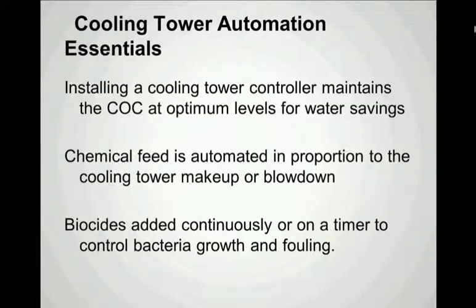So in essence, cooling tower automation is a big help in terms of keeping the cycles of concentration at optimum levels for water savings. It also helps us manage the chemical feed to make sure that it's automated and proportionate to the cooling tower makeup or blowdown, so that we're not overfeeding or underfeeding the chemicals if that's a problem. And also the biocides that are required to keep the water sanitary can be fed via the controller so that they're added continuously on a timer, so that we make sure that we keep on top of that, and the water quality, from a biological standpoint, is within our specifications.